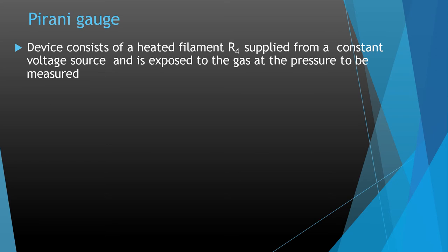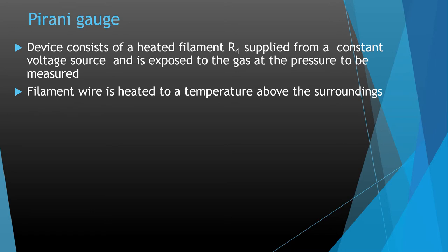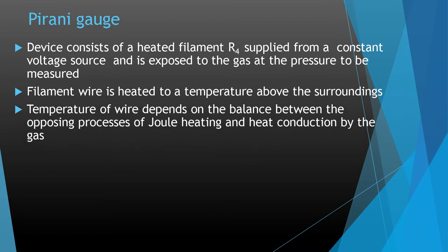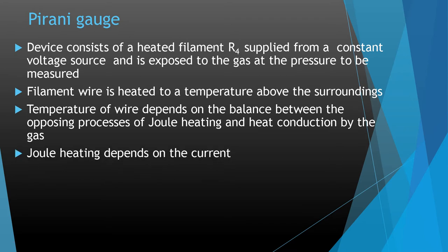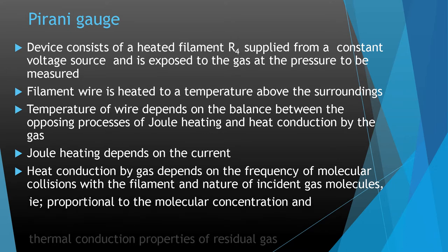The device consists of a heated filament R4 supplied from a constant voltage source, exposed to the gas at the pressure to be measured. The filament wire is heated to a temperature above its surroundings. The temperature of the wire depends on the balance between the opposing processes of Joule heating and heat conduction by the gas. Joule heating depends on the current, while heat conduction by the gas depends on the pressure, frequency of molecular collisions with the filament, and the nature of the gas molecules — proportional to the molecular concentration and thermal conductivity of the residual gas.